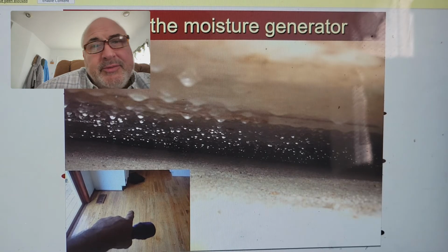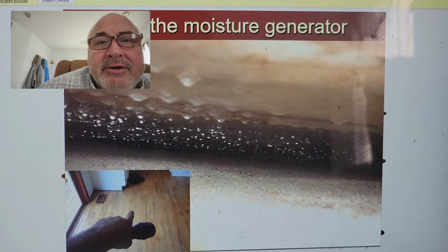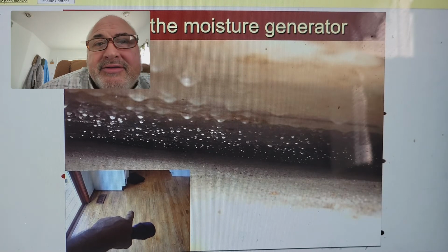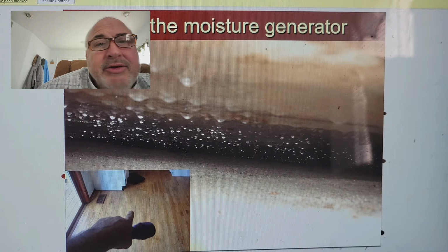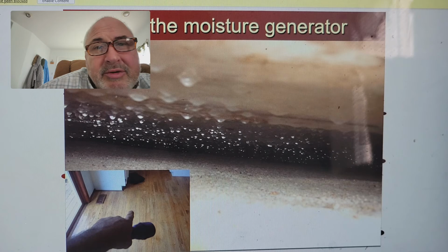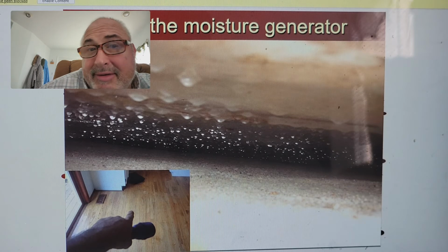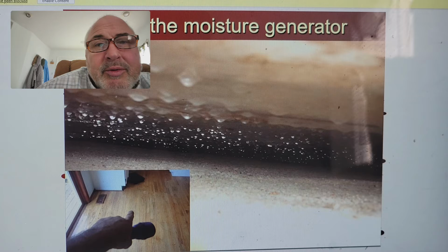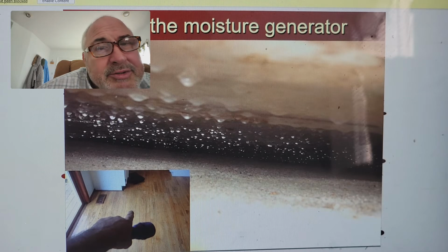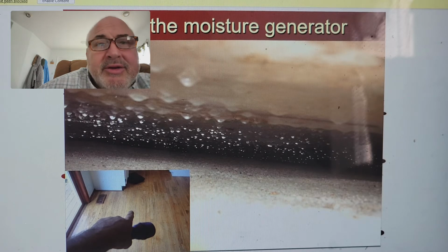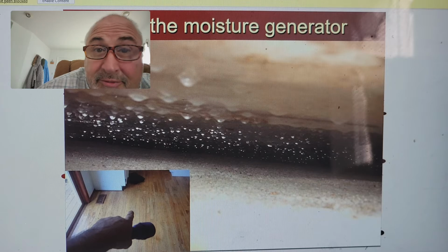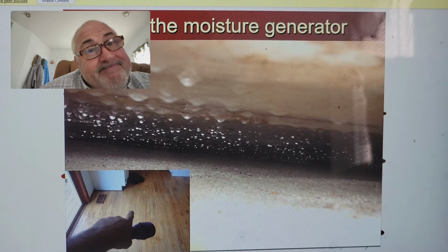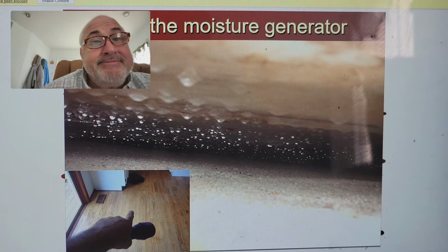And so this was the problem. It was that the soil underneath the slab on grade had settled, and then there was communication with the furnace, and then you had the perfect temperature. They weren't running a dehumidifier because they figured they didn't need one because they have a slab house, and the humidity would condensate, and then that became the water source, and then that became the humidity that went up into the house. So it was almost like a natural humidifier, and they're probably getting some moisture from the soil below through damp rise. And so, how do you fix this problem?